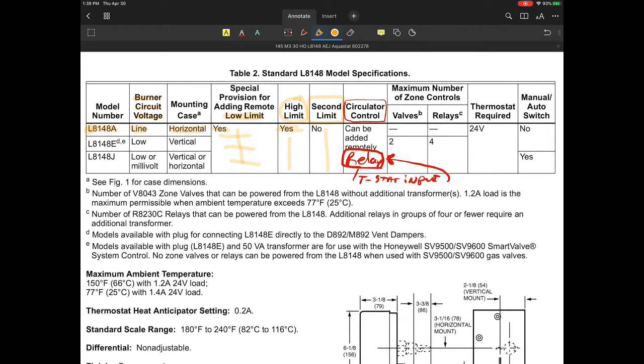All right, max number of zone controls that can be used on here. This is probably the one you really need to pay attention to, because we're the ones who go out on these sites and wire up zone control valves. What they're telling me is that on the line voltage burner circuit application, there is no provision whatsoever that allows you to control any type of valve or relay for any type of zoning. That has to be done externally. So this relay Aquastat, this L8148A, has no ability to power any external controls. That means if you've got a zone valve and you say, well, the Aquastat has a transformer, I want to just use that one, it will not work.